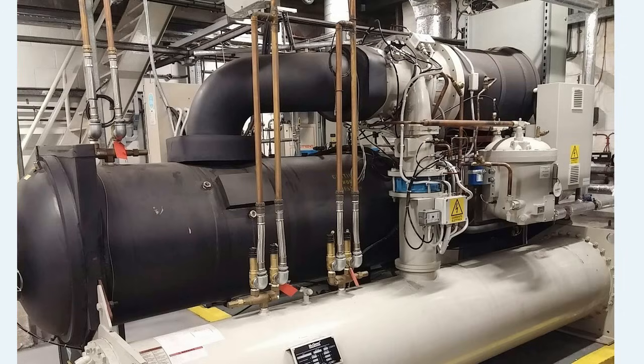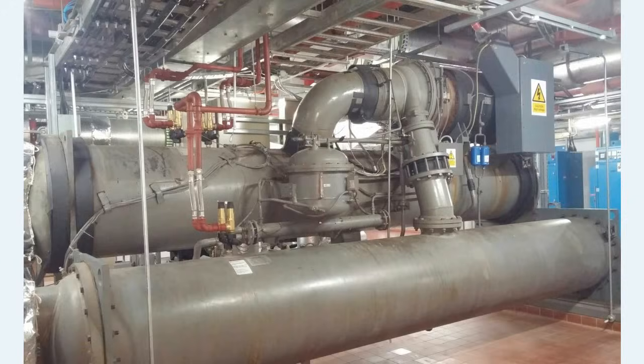A real world example of the compressor and how it would look if you walked into a plant room would be like this. So as I was saying, you've got the suction line and the discharge line here, and on the very top you've got the compressor hidden behind all these cables and pipes in this example. There's another example here of a much larger and older chiller, again mounted on the top here. It's just a slightly older version, and it's using a different refrigerant, and you can tell that by the size, but we'll have a look at that in detail later.